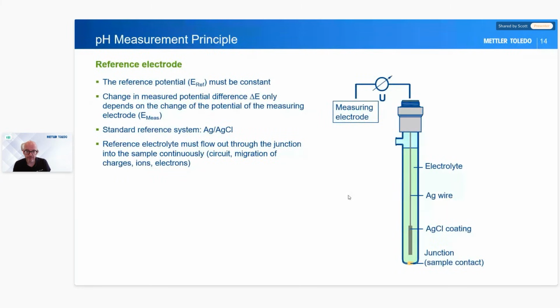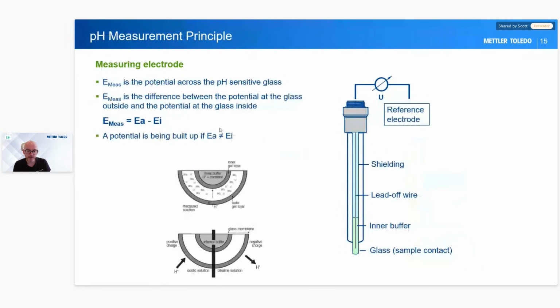Once we've got a reference electrode, the next part is our measuring electrode, and the measuring electrode measures the potential across a pH-sensitive glass. In the tip of our bulb, which is normally a glass bulb at the end of our measuring electrode, we have a lovely piece of glass, and this glass allows the transfer of H+ ions in and out of the glass. Inside this glass is a buffer that we can't touch or use, it's sealed. On the outside of our glass bulb, we have a gel layer, and this gel layer is full of hydronium ions, those H+ ions, ready to go.